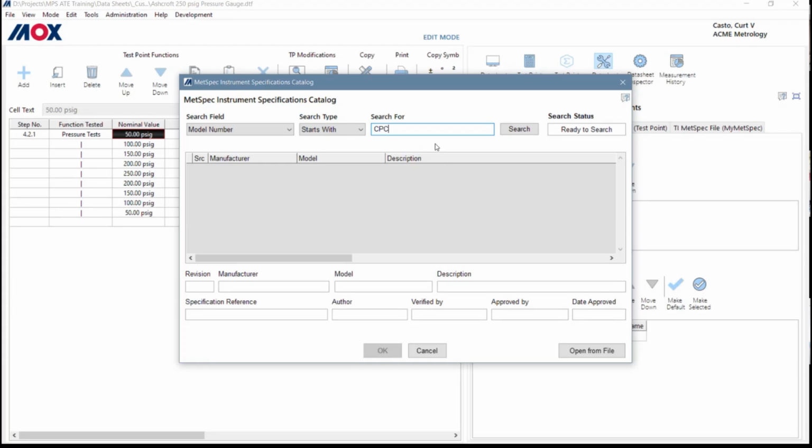And then when you're done, if you don't have the rights to approve them, you can just email the file to somebody that does, and they can go in and do their review and all that stuff. And if they approve it, then they can approve it into the database and it'll be ready for use. In the case of spec sheets, they'll be ready to be used with data sheets. And in the case of data sheet templates, they'll be ready to use for calibrations once they're approved into the database. And all of that is audit logged and revision controlled. You can have multiple revisions for both spec sheets and data sheets. So if you change it, it retains the old versions. So you have all that control.